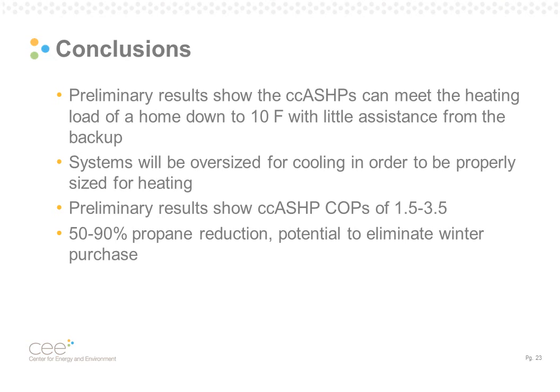So in conclusion, we are seeing preliminary results that show that the cold climate heat pumps can meet the heat load of a home down to 10 degrees Fahrenheit with some assistance from the backup. These systems are sized for heating, which means they are going to be oversized for cooling. Our preliminary results do show coefficients of performance for these three units between 1.5 and 3.5.